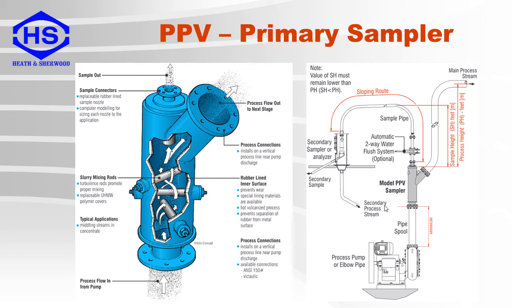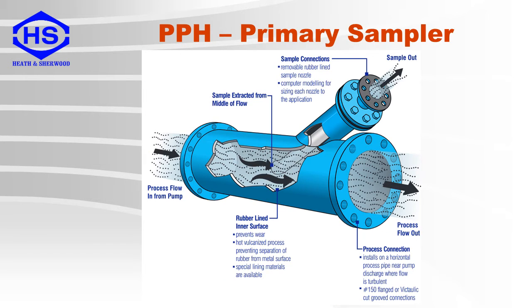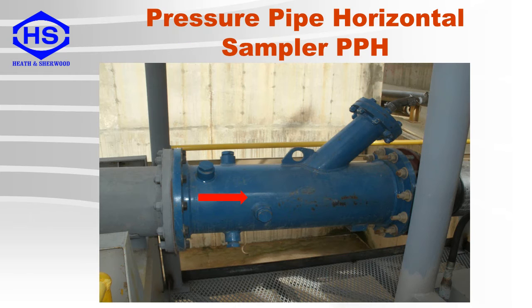It should be stressed that for this system to provide a sample, the maximum height of the sample piping must be less than the maximum height of the process piping. A version of the PPV without mixing rods is also available. This version of the pressure sampler is designed for horizontal installations, where the process inlet and outlet are on the same plane whereas the sample goes off at an angle. Here is an installation example of a horizontal pressure pipe sampler with mixing bars.